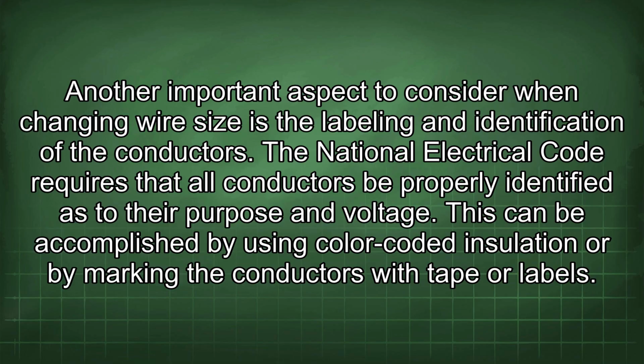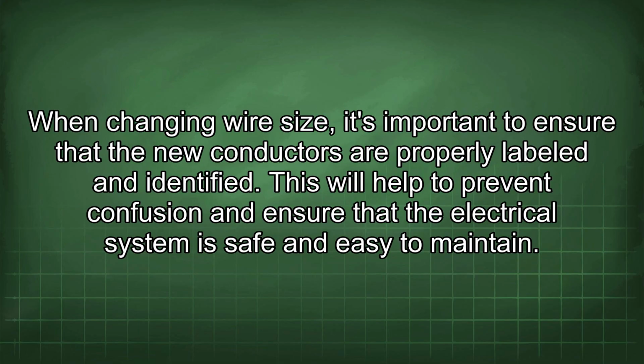Another important aspect to consider when changing wire size is the labeling and identification of the conductors. The National Electrical Code requires that all conductors be properly identified as to their purpose and voltage. This can be accomplished by using color-coded insulation or by marking the conductors with tape or labels. When changing wire size, it's important to ensure that the new conductors are properly labeled and identified. This will help to prevent confusion and ensure that the electrical system is safe and easy to maintain.